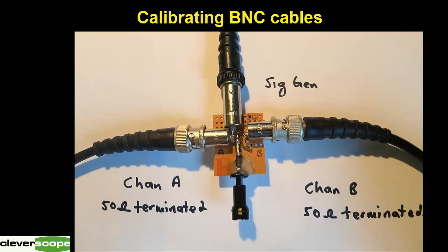Cleverscope can calibrate standard probes as well as calibrating BNC cables. We assume that the cable is 50 ohm terminated. This is automatically detected by the FRA software. The advantage of BNC cables is that their bandwidth is much higher. We can do measurements on components up to 65 MHz.